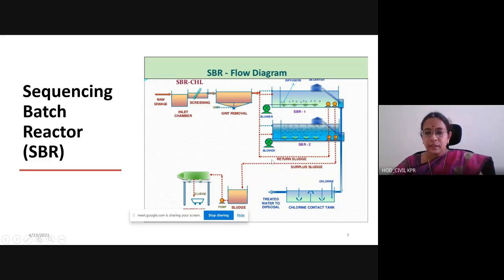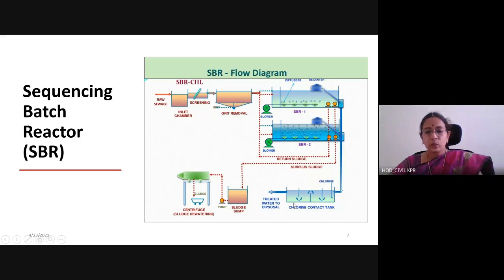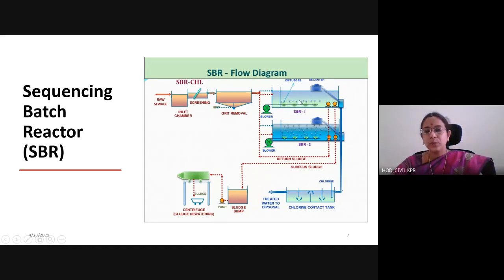The surplus sludge is taken out through a sludge pump or sent to a centrifuge for sludge dewatering, and then taken out as manure or for disposal. SBR1 and SBR2 can be followed by SBR3, SBR4 depending upon the characteristics of the wastewater. From all these treatment stages, it can go to a contact tank if required, and then to filtration, or directly to disposal. The difference between a normal STP plant and a Sequencing Batch Reactor is that primary settling, aeration, and secondary settling are all put together, so no separate maintenance or separate components are needed — it is a compact system.